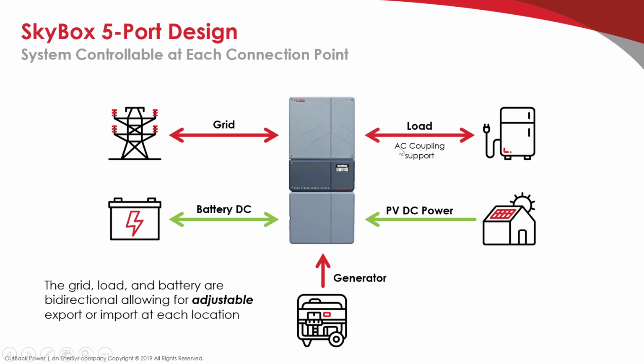And with our latest version of software, I believe it's 1.4.5, it now supports AC coupling, which we'll talk a little bit more about momentarily. So we have this 5-port design. It's not a bidirectional H bridge like our inverters and many of our competitors' inverters are. It's got some pretty sophisticated power flow management inside of it.